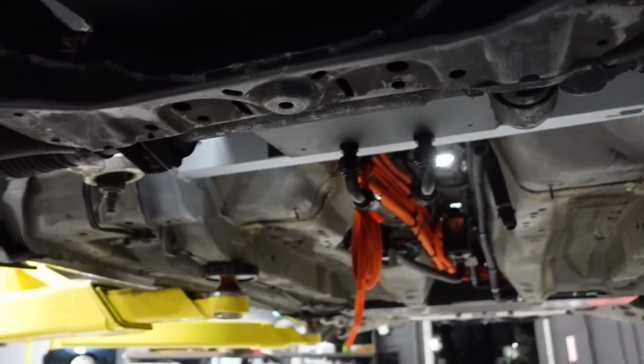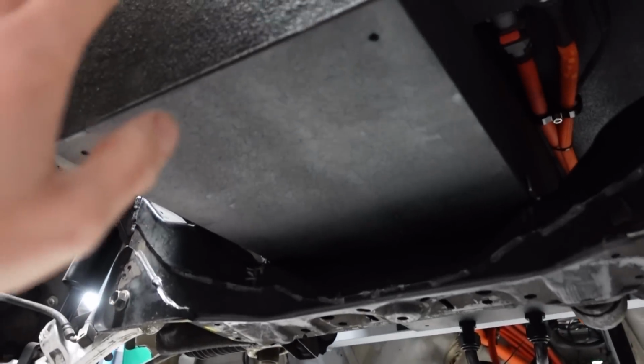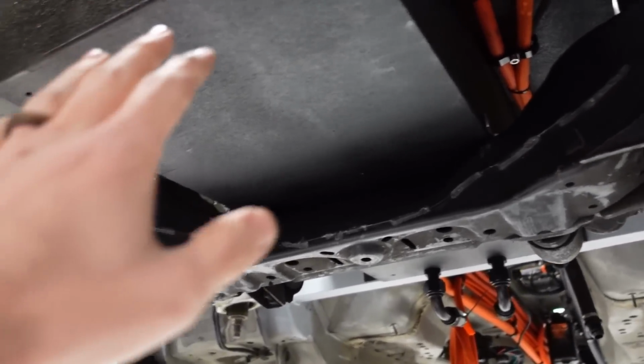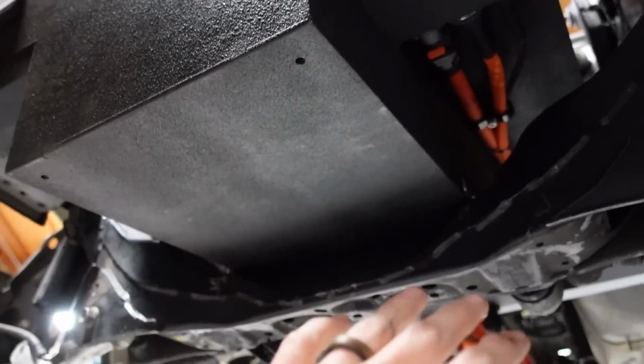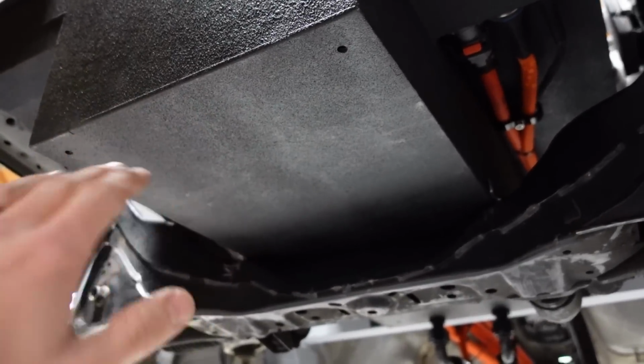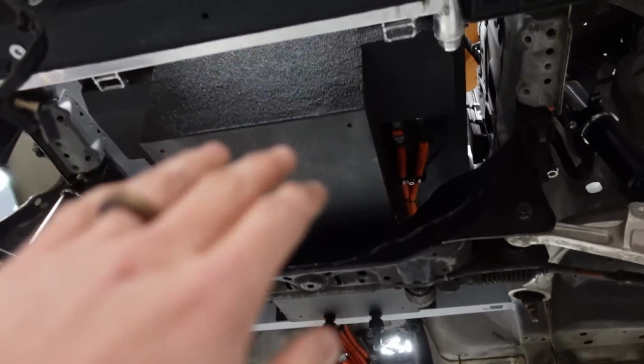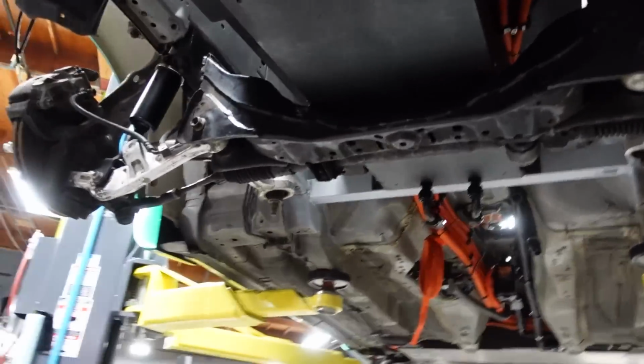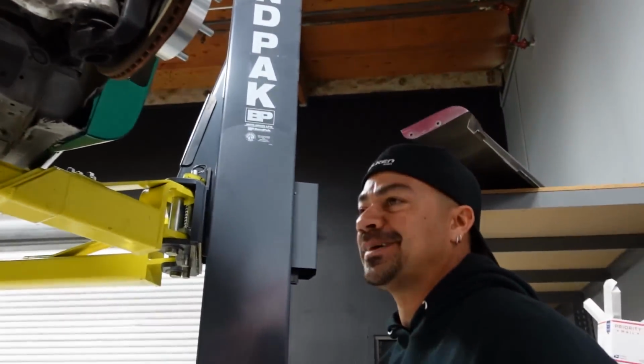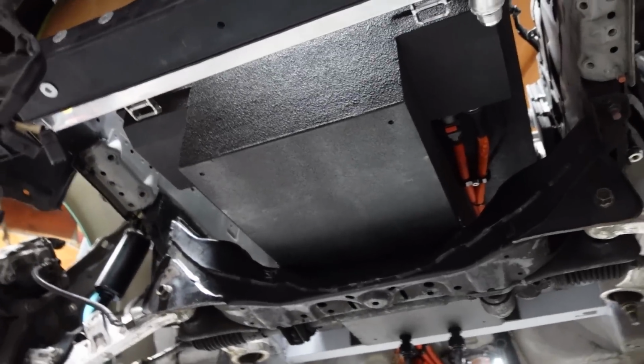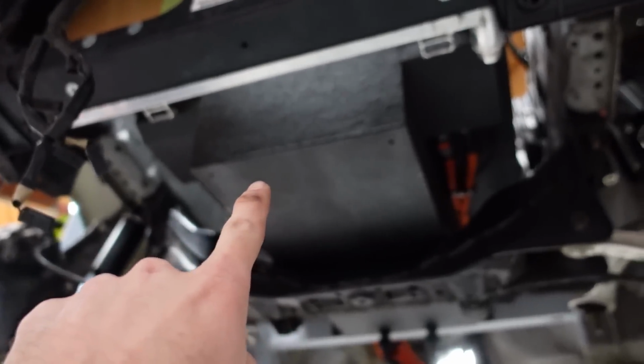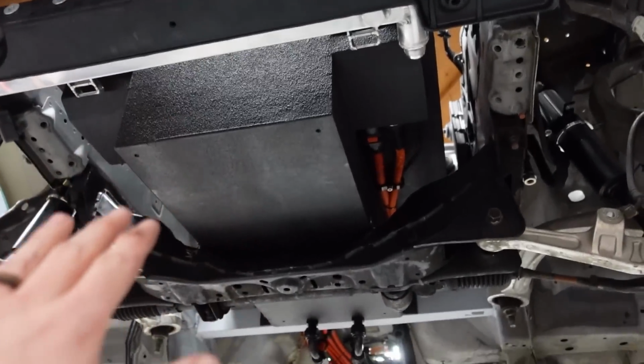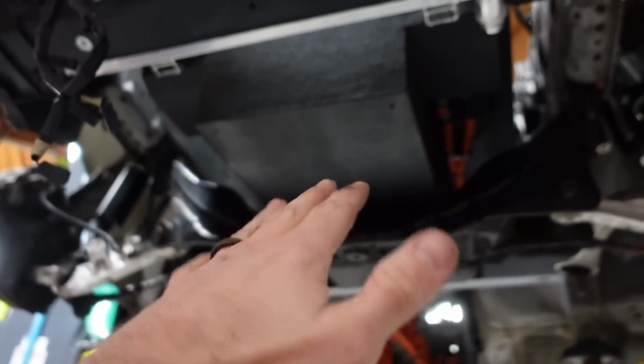Each of those groups runs at 4.15 to 4.2 volts fully charged. If you multiply the 6 batteries inside each module by roughly 4 volts, you get about 24 volts per module, just for simplicity. Since we have 12 of those 24-volt modules in this box, once we're done stacking them in series, we have 300 volts coming out of here. Does that make sense? Very simple.